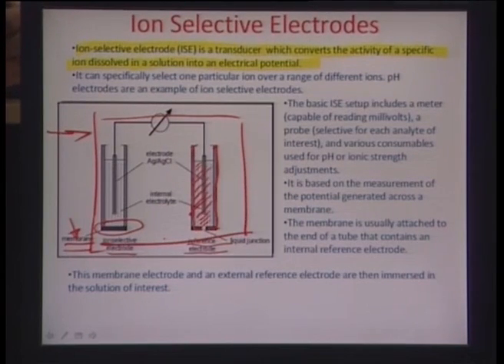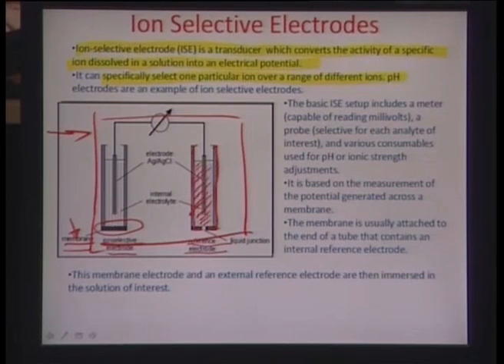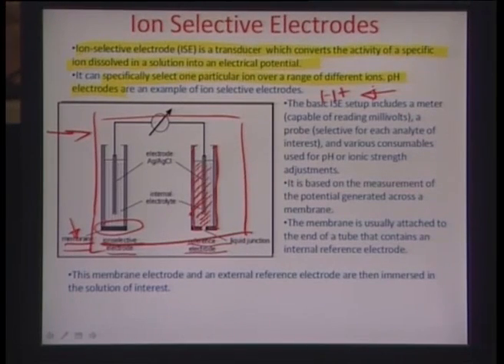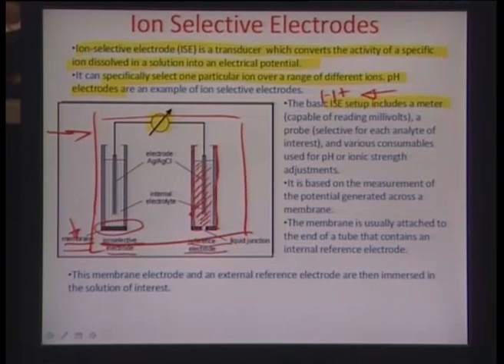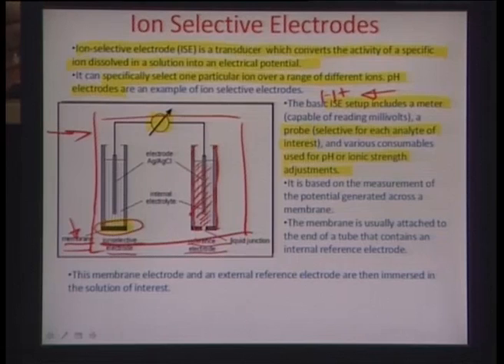The job of the ion selective electrode is to specifically select one particular ion over a range of different ions. Suitable examples are pH electrodes, which pick up only hydrogen ions and leave the others behind. The basic ISE setup includes a meter, a probe selective to each analyte — the selection done by the membrane — and various consumables used for pH or ionic strength adjustments.